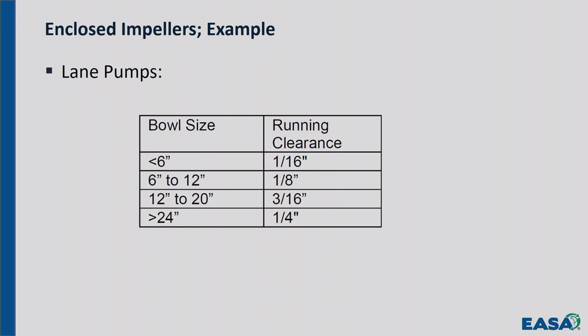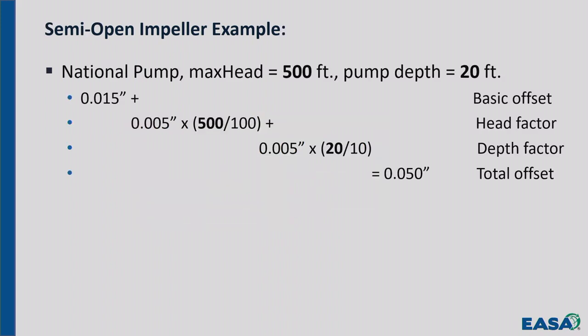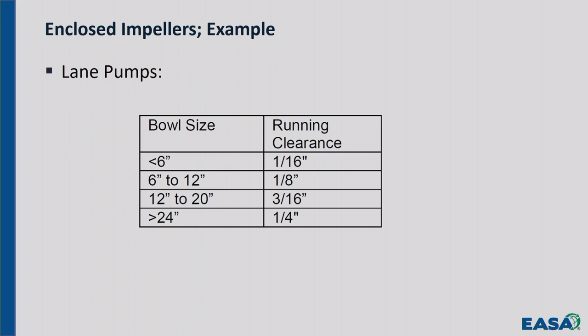When you get to a semi-open impeller, here are the specs for National pumps. They want 15 thousandths clearance plus 5 thousandths for every 100 feet of pump head plus 5 thousandths of an inch for every 10 feet of pump depth. So this is what Lane specifies for their pumps for setting the lift. So I've got 500 feet of head and a 20-foot deep pump. I need 15 plus 5 times 5 plus 5 times 2 equals 50. My clearance, my lift, is 50 thousandths. I've got to raise it up 50 thousandths. So with an open impeller, you're talking in thousandths of an inch. With a closed impeller, you're talking in 1/16 of an inch. Okay?